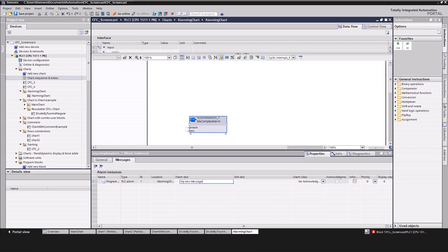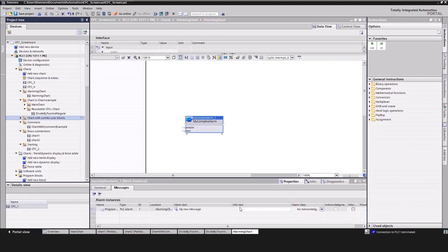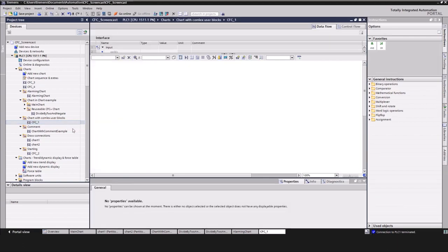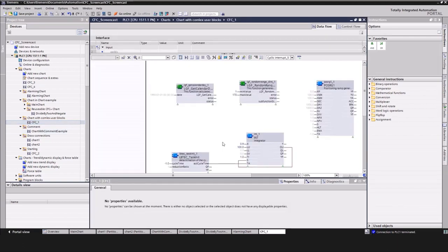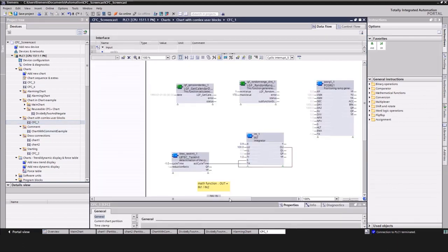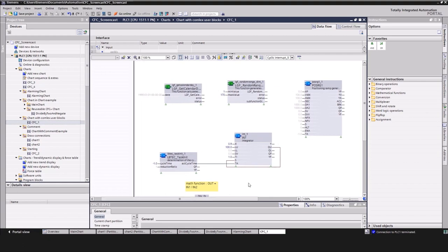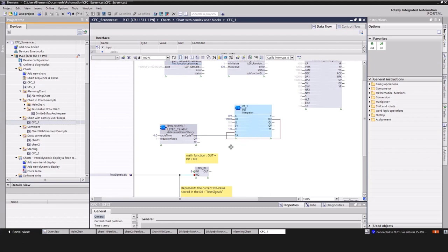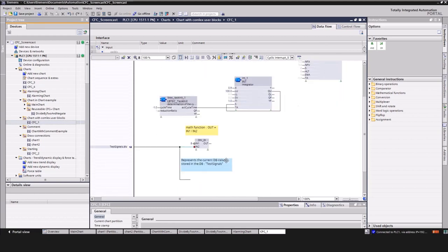As we have completed the user program, I will show you how the CFC looks like when you go online on the controller. The initial download requires a complete software download that includes a PLC stop. Smaller changes can be downloaded while the PLC is still in run. I have already executed the initial download. I just have to go online.